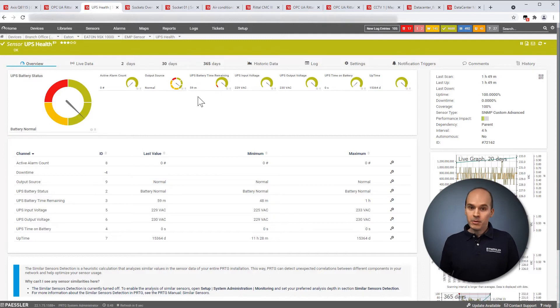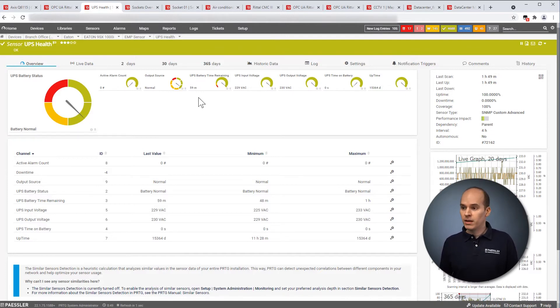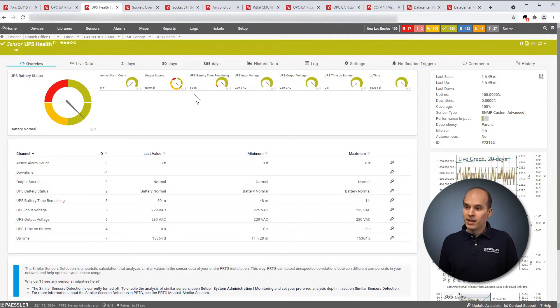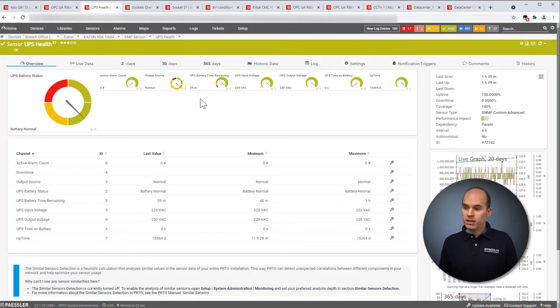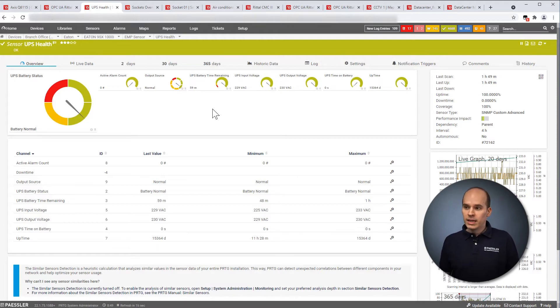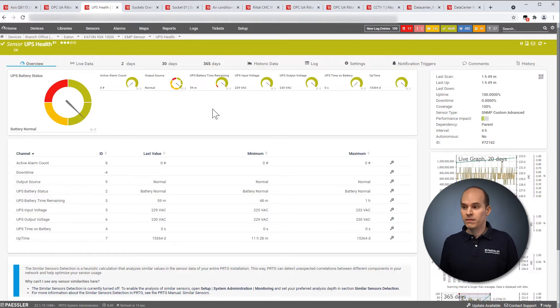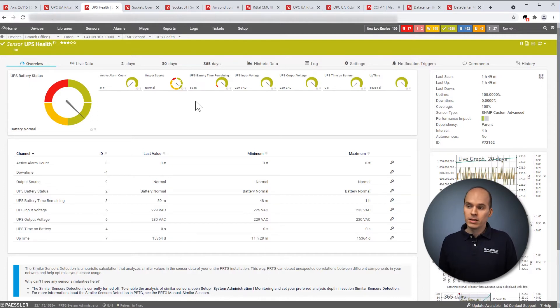Another important information is the UPS battery time remaining. So you can read out this information from your UPS. And in this case, it's 59 minutes. So the UPS can take over the IT for 59 minutes. And you can decide during that time you can shut down your servers. Or it depends on your security level. Maybe you have installed a power generator. Then you can, of course, bridge the time to the power generator.